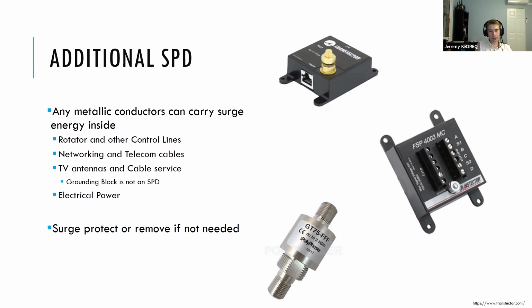And so looking at all the metallic conductors coming in as a potential source for surge current, you kind of have two options, right? Surge protect them or remove them. And that's just a good best practice, and something we look at a lot in the industry: if something's abandoned, it's not there anymore, it's kind of a liability if that's a metallic conductor coming into your shelter. So removing stuff that isn't needed is definitely a best practice for surge protection.